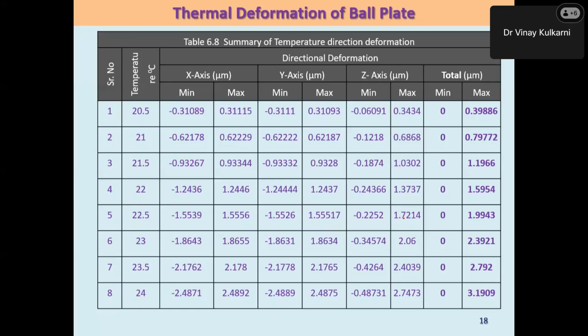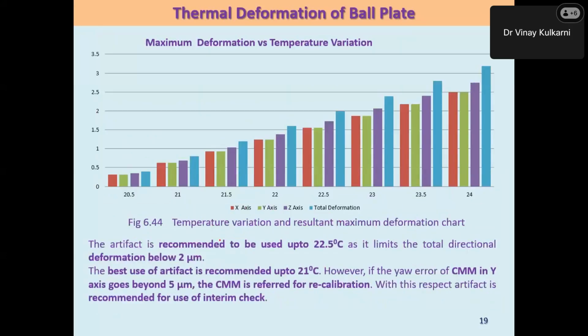And at the same time, as you can see here, the artifact is recommended to be used up to 22.5 degrees centigrade. It holds its position up to 22.5 degrees centigrade, as it limits the total deformation below 2 microns. Below 2 microns is a standard for any artifact to keep the flatness intact, and other things.